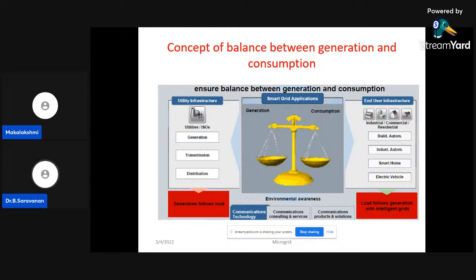The only electrical parameter we monitor is frequency. By knowing the frequency, we can find the generation-load difference - the difference between generation and consumption. So we always ensure the generation and consumption, meaning load, are balanced. If it is balanced, the frequency stays within limits. Even a small variation in frequency is allowable; it should be within plus or minus 0.5 hertz.